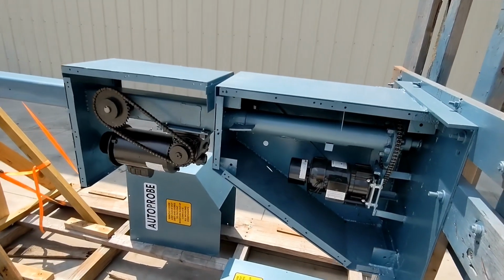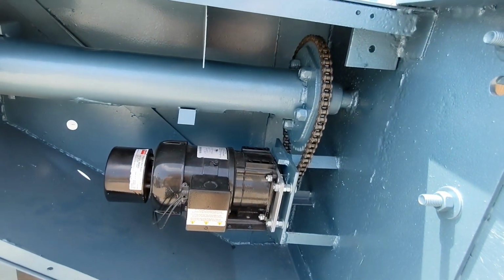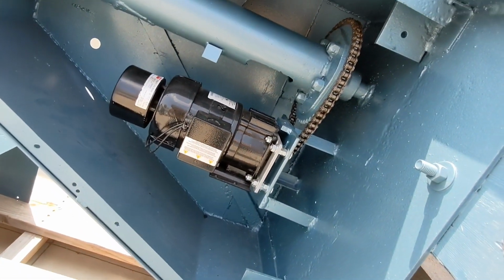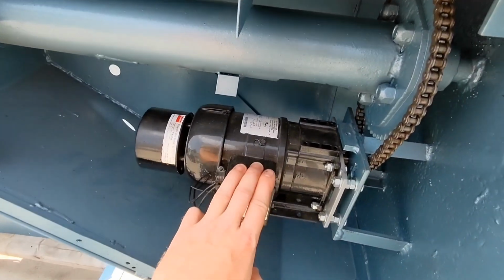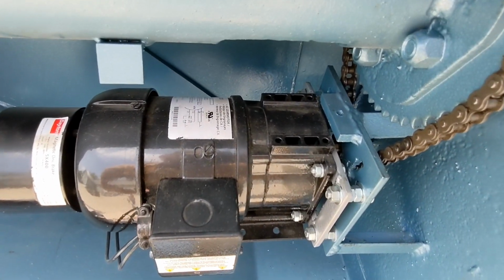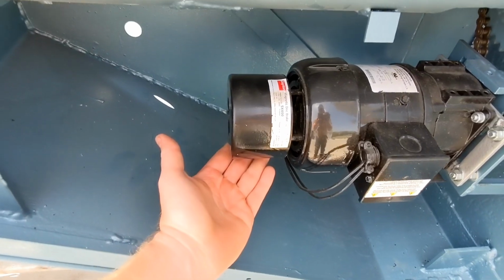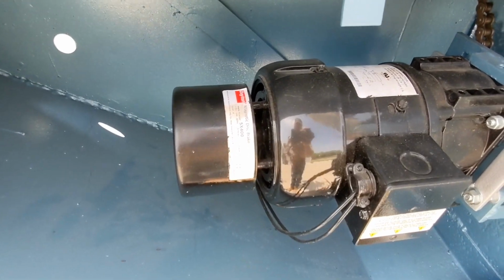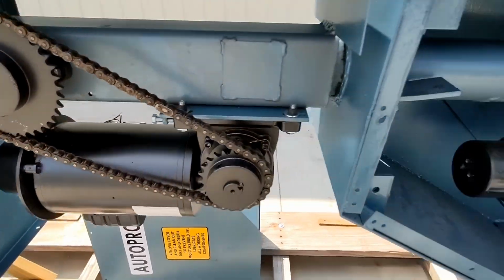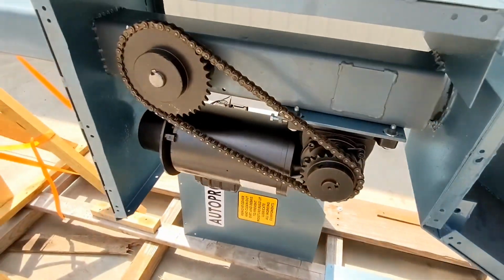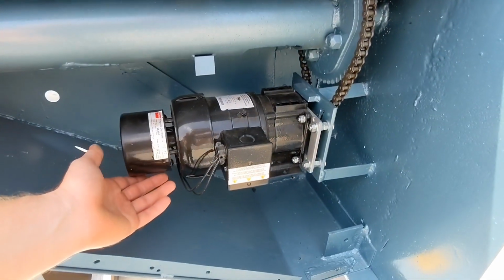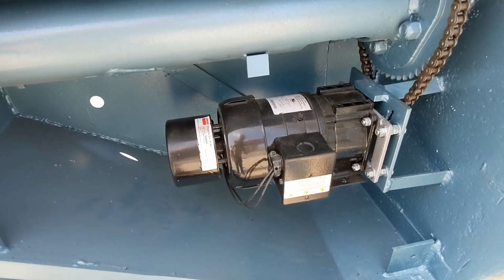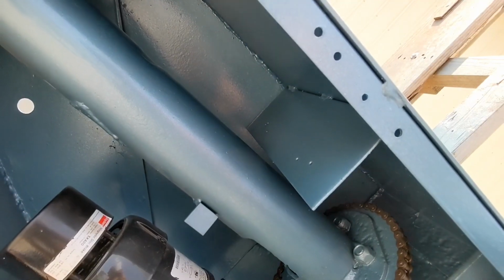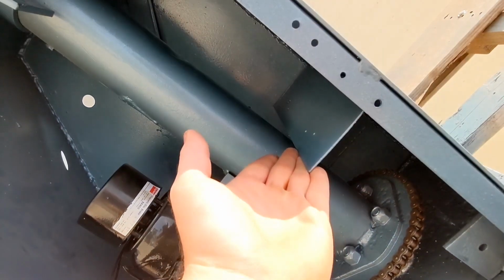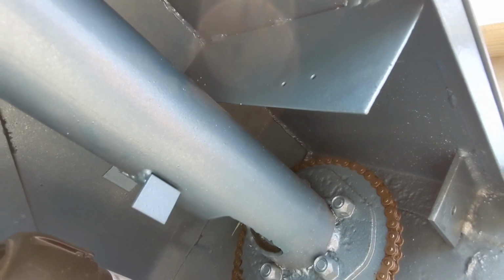All right, we've removed the inspection covers so you can see the internals of this probe. The motors are in great shape. We had them checked over by a certified motor technician. He went through the brakes, checked them over, replaced the brake pads and both of the little brakes on the back sides of these drive motors. The brake ensures that the motor stops instantly once power is disconnected. Later in the video, I will discuss how easy it would be to wire this unit up with the proper micro switches.